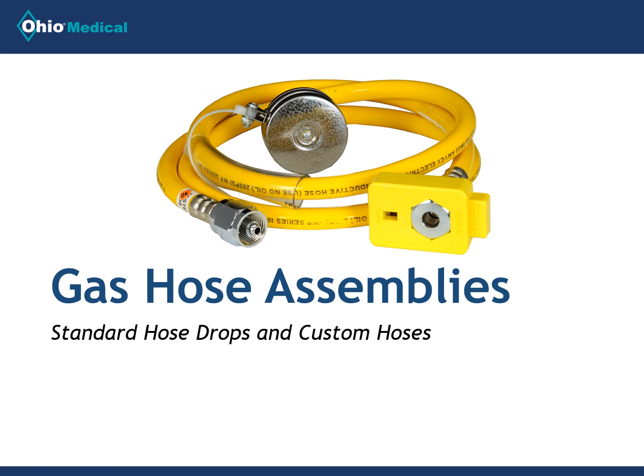Our hose assemblies are available in standard hose drops and can also be customized to meet a facility's specific needs. Our hose assemblies are manufactured with medical-grade anti-static PVC tubing, which is reinforced with polyester braiding. The hose assemblies are normally made with DISS female connections on one end that is connected to an outlet. The other end is a male DISS or female quick connect coupler with check unit. The standard length is approximately 5 feet, with the internal diameters being 1/4 inch for pressurized gases and 5/16 of an inch for vacuum and WAG hoses.